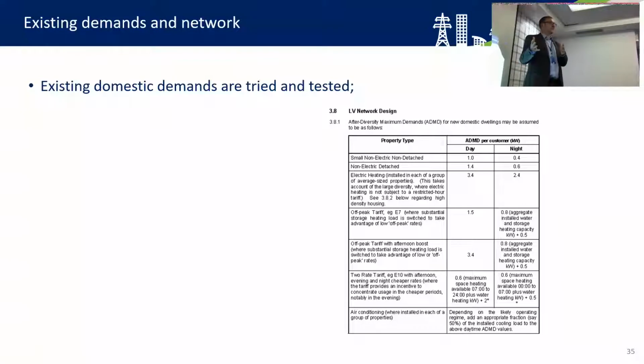These are in kVA. So if we've got a 100 property housing site, we'd know we need 100 kVA, which isn't a lot for 100 houses. But this is tried and tested and proven. The ENA have done lots of monitoring, we've done monitoring, and you can bet your bottom dollar if you go and read the MDIs of a substation with 300 houses connected to it, the maximum demand will be between 300 and 400 kVA. That's simply because of the diversity factor - not all 300 properties will have a shower running at the same time, not all of them will switch on together.